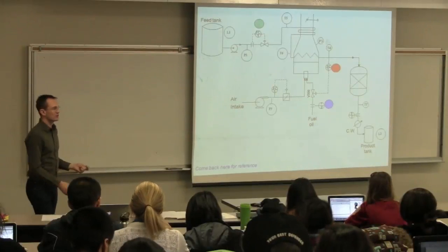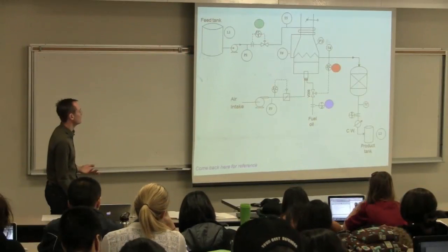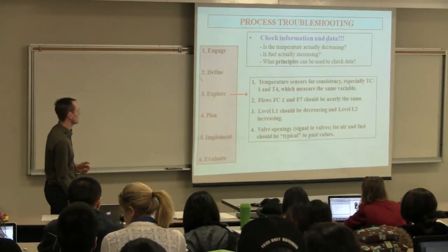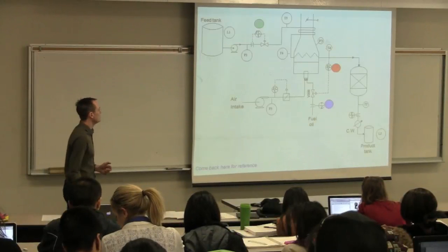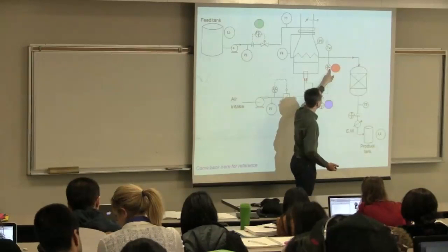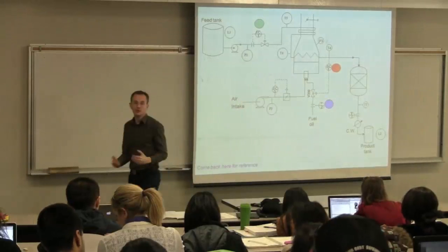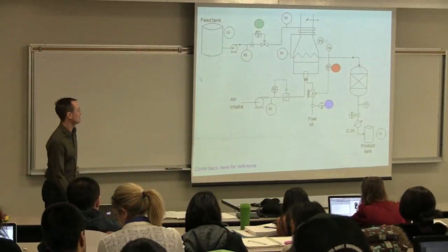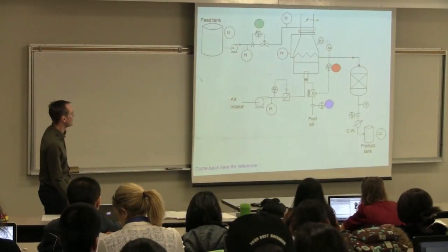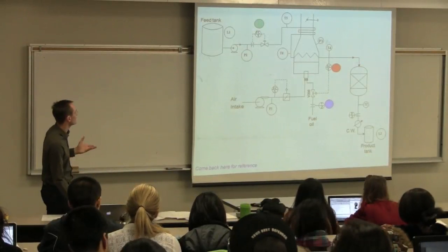The expert system will respond based on their case study, where they know the absolute truth. They will tell you, in this case, yes it is. So TC1 matches temperature 4. So immediately there, you know that the drooping temperature that's the problem is also going to be seen in T4. So we can rule out the fact that it's the sensor that's an issue. Okay, so we'll come next to how we work things out. Now we're simply exploring the problem, checking consistency.